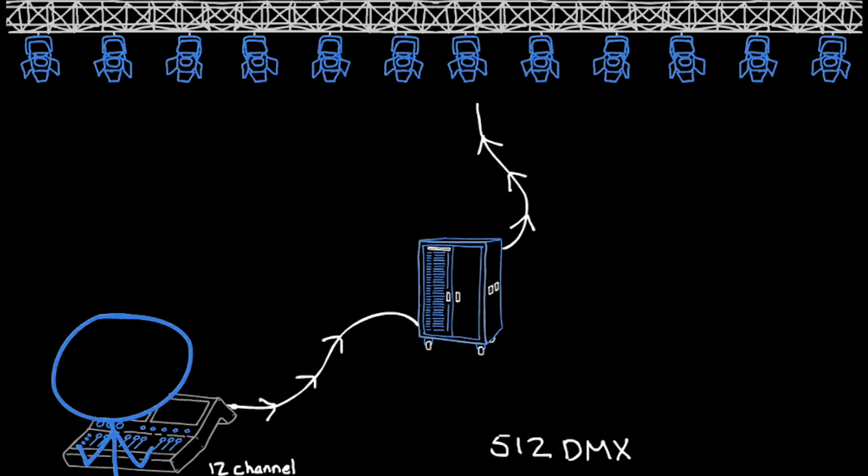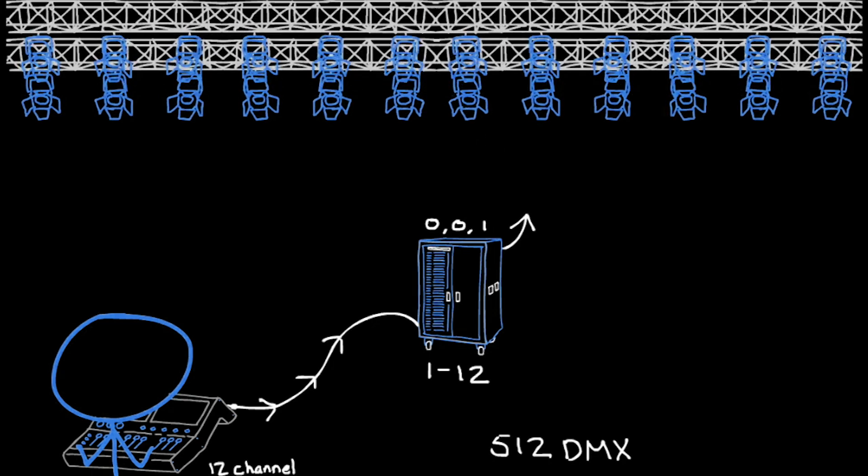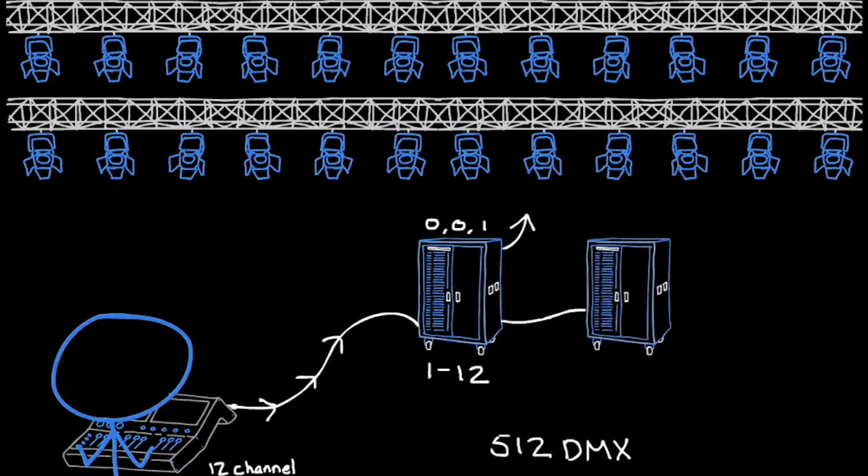The dimmer will have a digital thumbwheel. We dial that at 001, meaning dimmers 1 through 12. Let's say the theater increases their budget and buys 12 more lamps. They need to buy another dimmer. Well, if this dimmer is 1 to 12, this dimmer would be 13 through 24.